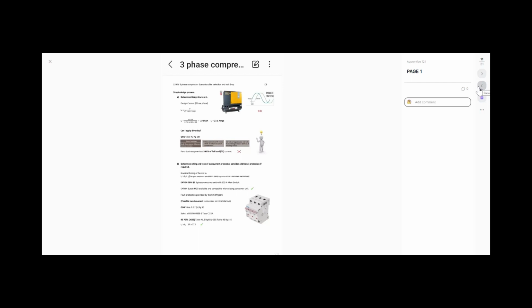I've got to think about regulation 433.1.1, which considers overload protection. We looked at this last week. We've got to make sure that the rating of our protective device is equal to or greater than our design current, because if it's the other way around, you're going to get nuisance tripping from your overcurrent device. So I've got a design current there of 27.1 amps. I've got to select a circuit breaker with a current rating equal to or higher than 27.1 amps. So we're going to select a 32 amp device because that's the next size up.